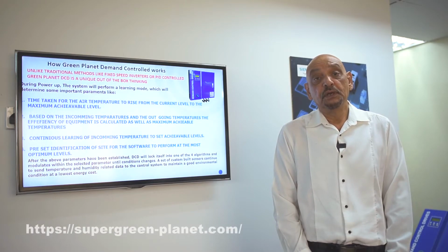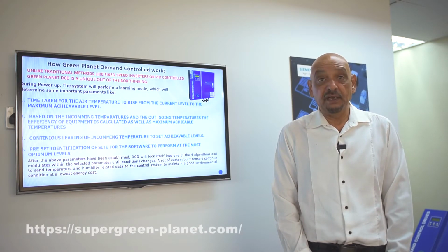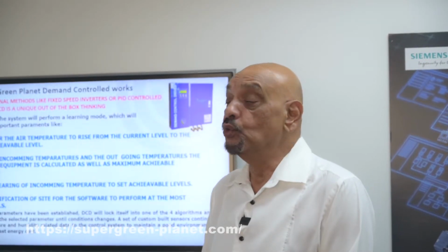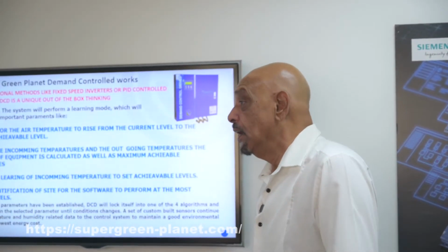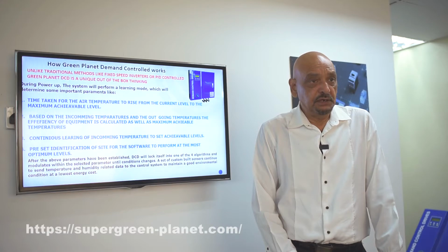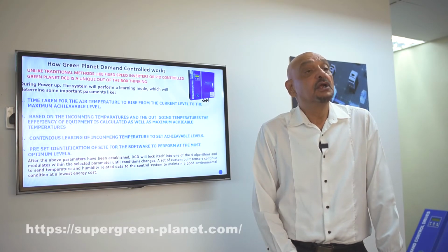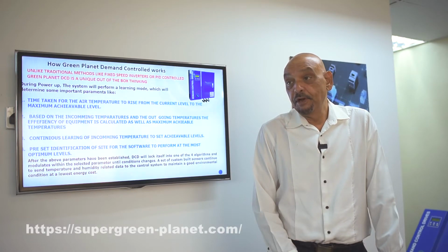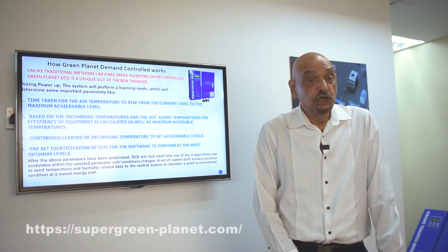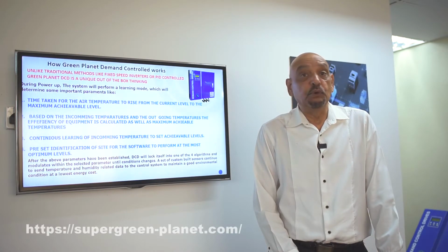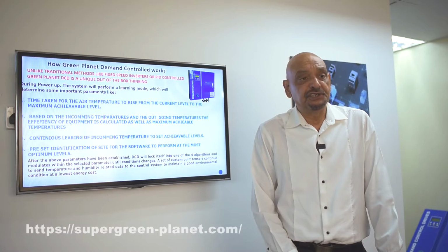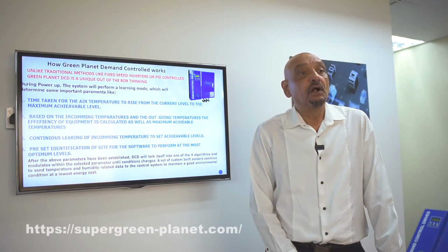As far as your cooling tower is concerned, you only have one motor and a fan, and it is the evaporation process that cools down the water. The benefit you are going to get is similar to what I have mentioned for the air handling unit. You will still get soft starting. Your fan speed is well managed. You will reduce evaporation as far as your water is concerned. You will save money not only on electricity, you will also save money on water, for example, which is lost through evaporation.